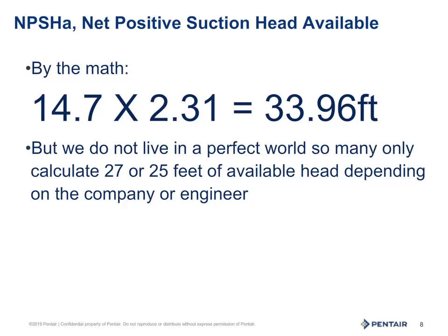We need to account for plumbing that may allow small amounts of air into the system. Pump assembly and machining has tolerances. Pumps will wear with age. So the industry standard is 25 feet, though some may use 27. This is determined by the manufacturer of the pump or an engineer, for example. Myself, I would err on the side of caution, and I use 25 feet.